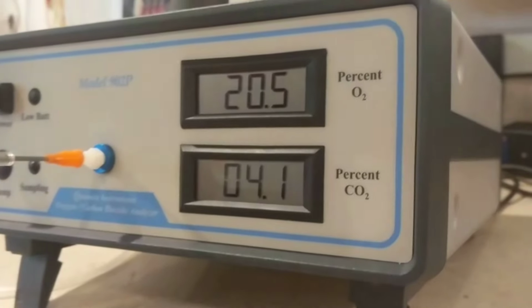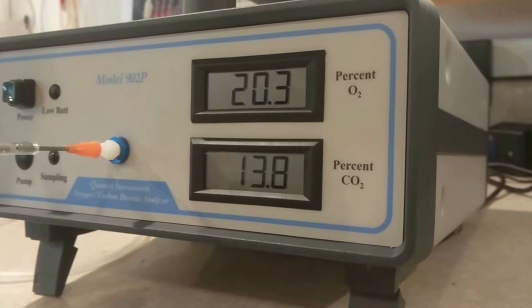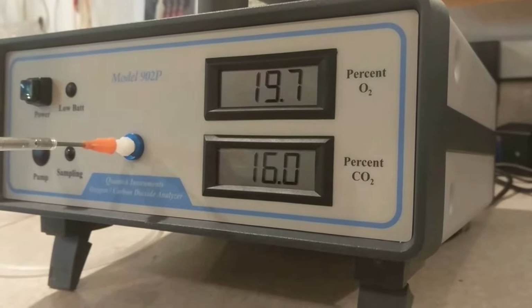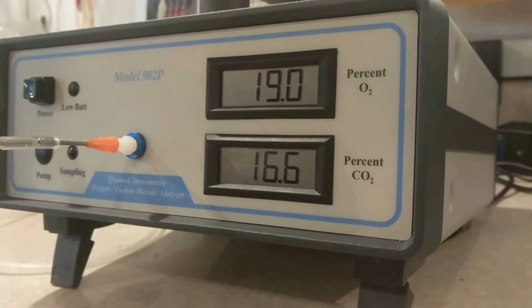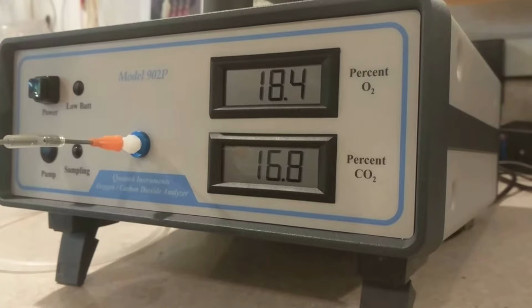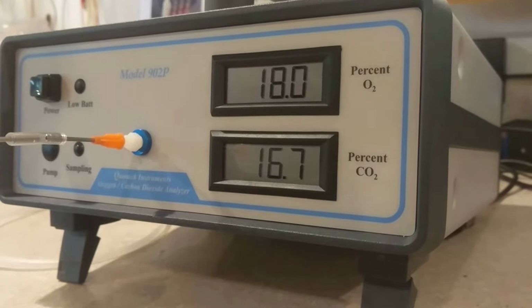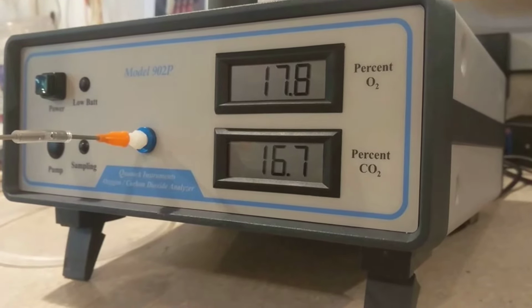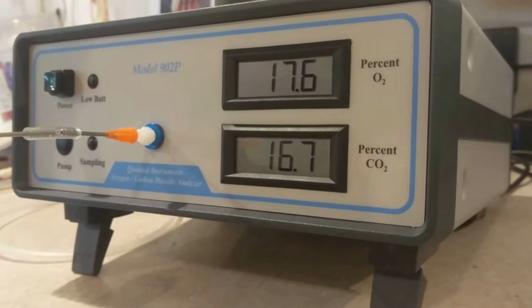And you could use a smaller syringe. 60 cc's is not necessarily the size that you need. The instrument only requires probably about 20 cc's of volume. The reason why I like to use 60 is because the margin of error will be smaller when you're dealing with higher volumes.